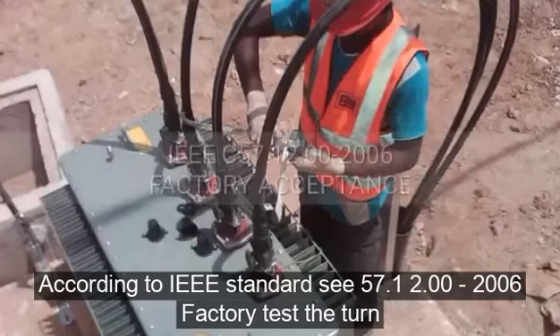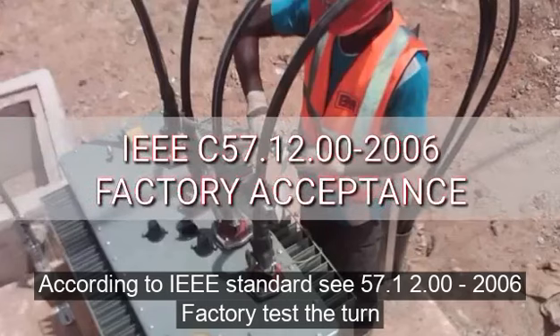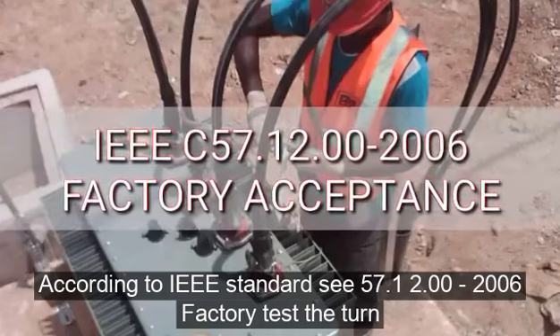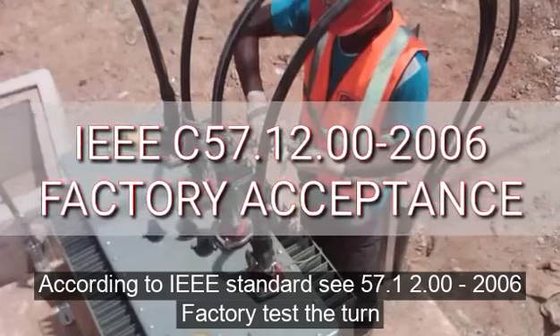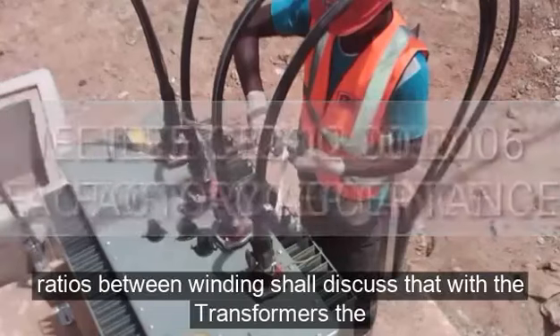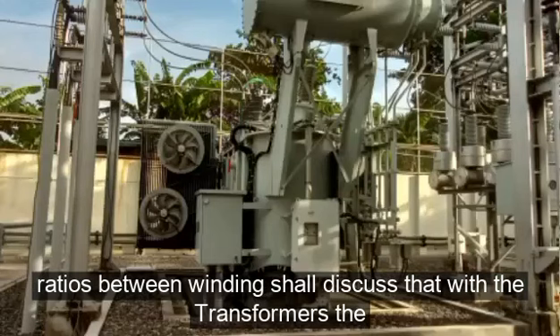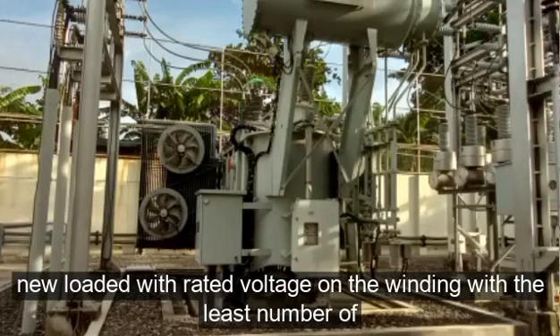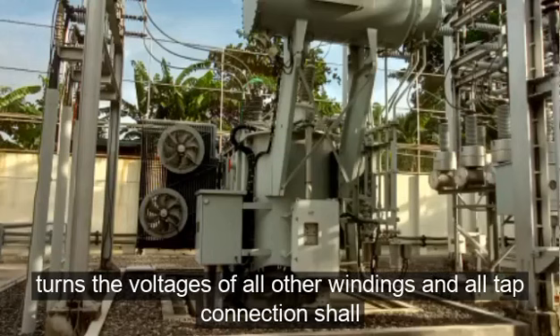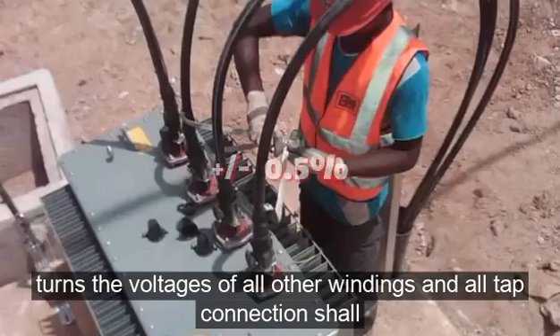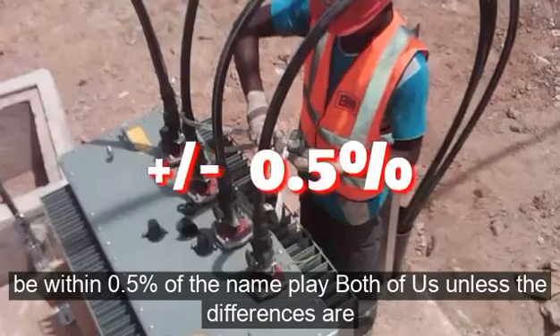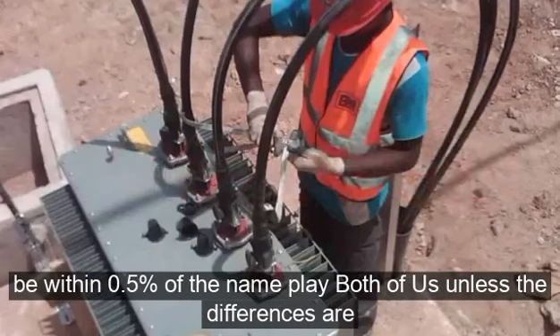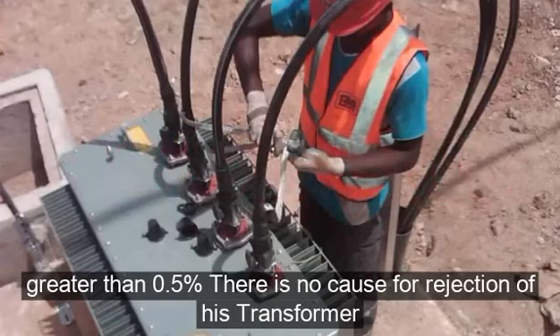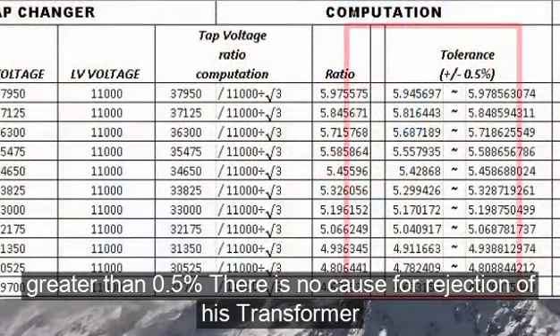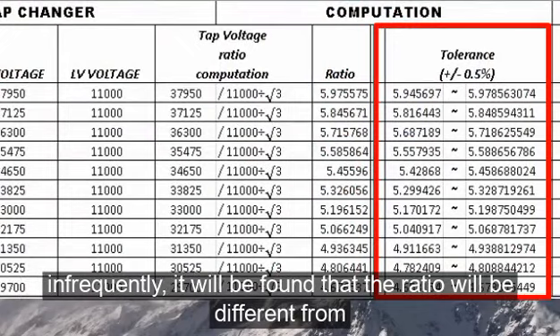According to IEEE Standard C57.12.00-2006 factory test, the turns ratios between windings shall be such that with the transformer at no load and with rated voltage on the winding with the least number of turns, the voltages of all other windings and all tap connections shall be within 0.5% of the nameplate voltages. Unless the differences are greater than 0.5%, there is no cause for rejection of this transformer.